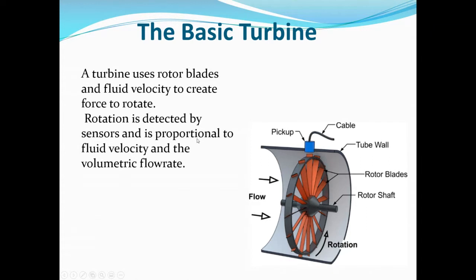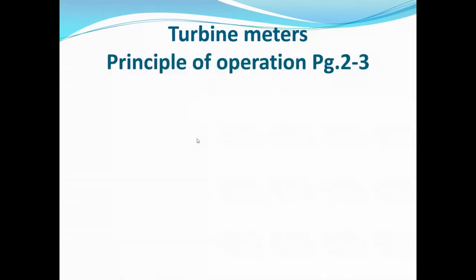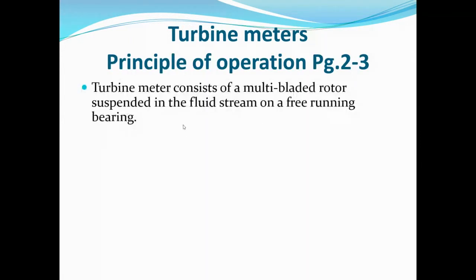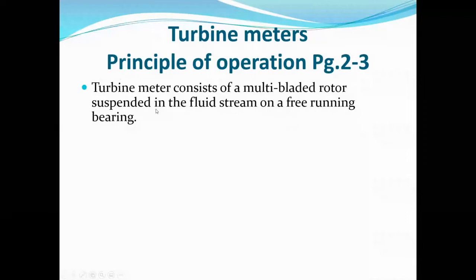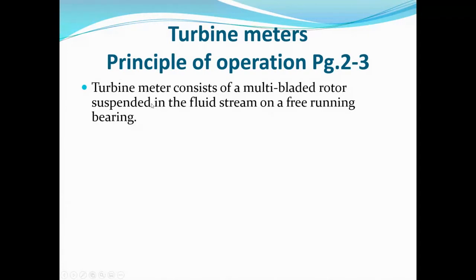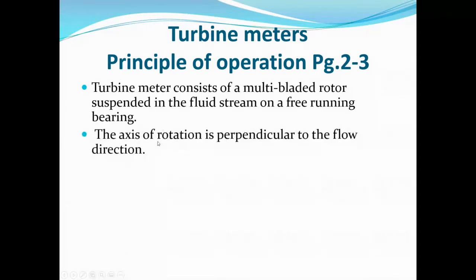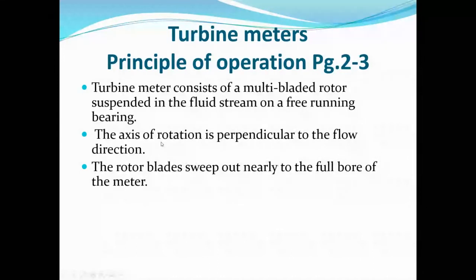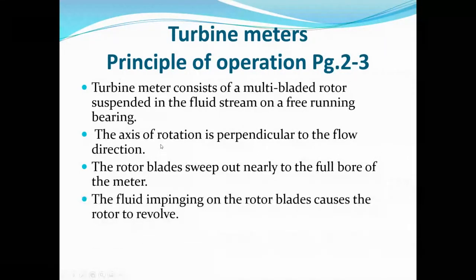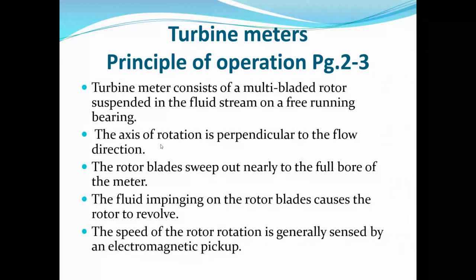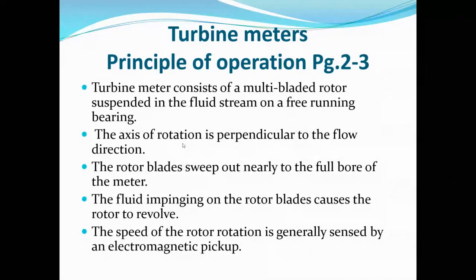In terms of complexity, turbine meters are not too bad — a little delicate but easy to understand. The principle of operation: a turbine meter consists of a multi-bladed rotor suspended in the fluid stream on a free-running bearing. The axis of rotation is perpendicular to the flow. The rotor blades sweep out nearly to the full bore of the meter, and the fluid impinging on the rotor blade causes it to revolve. The rotor rotation speed is sensed by an electromagnetic pickup.